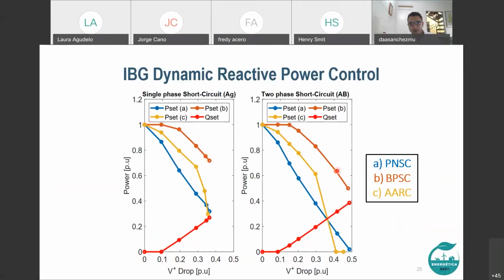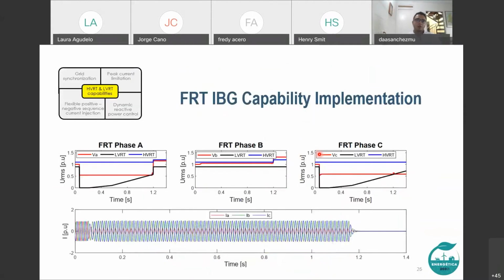Here is the BPSC. So finally, the fifth functionality, and it is the fault ride-through IBG capability implementation. This implementation is according to the Colombian code, and in this example we can see a single phase to ground fault that is not cleared for more than 1 second. When the phase C voltage overcomes its own low voltage ride-through curve, the inverter cuts off the injected current in a smooth way. Check out this. The inverter cuts off the current.